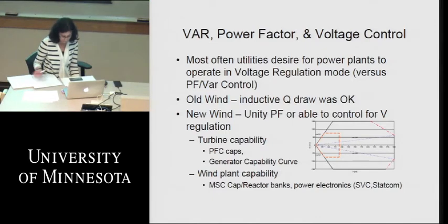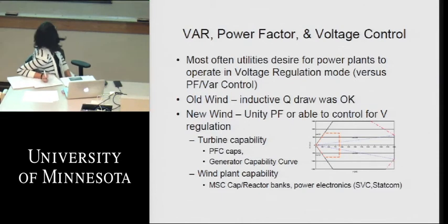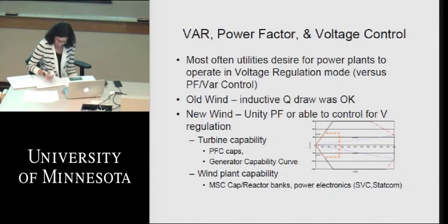So it depends on what type of turbine we have here. For the type 1 and 2s, we find power factor control with power factor correction capacitors, or power factor compensation capacitors. But for a type 3 or 4, we actually operate to a capability curve, an active-reactive power capability curve that looks something like the diagram you see there. It's not a D curve like a conventional synchronous machine. You've got the same sort of limitations on the stator and rotor winding heating that present the ultimate limitations, but you can only get so much apparent power out of the machine as the vector combination of active and reactive power.